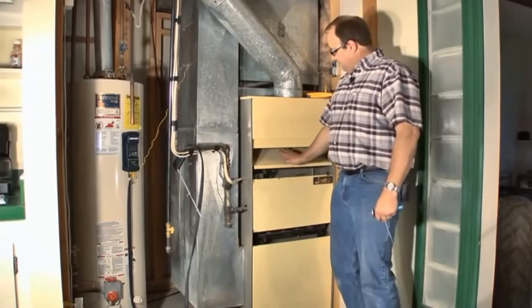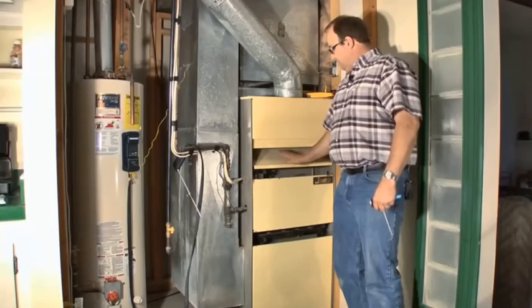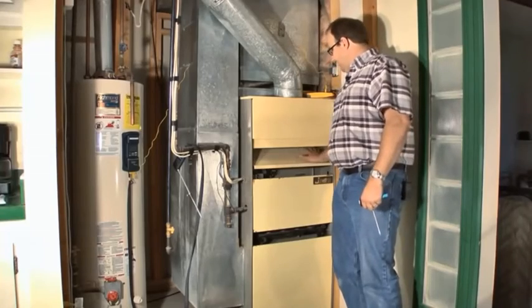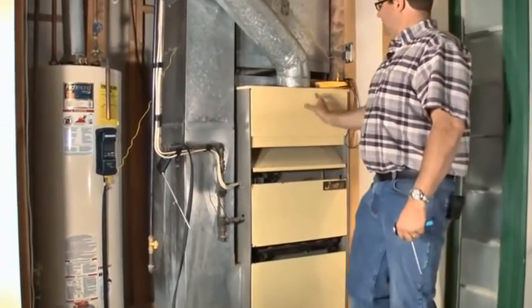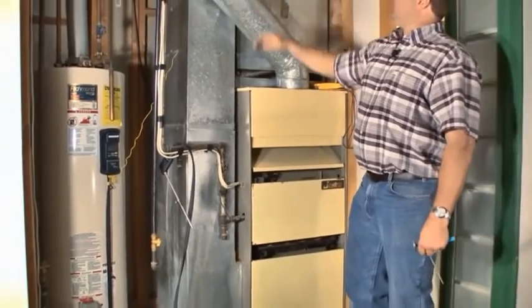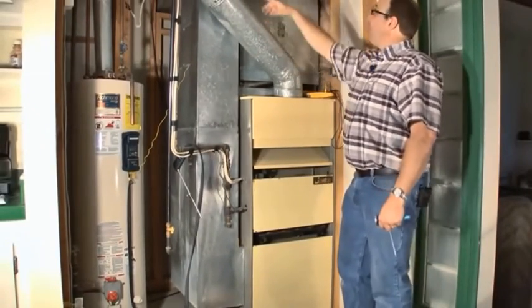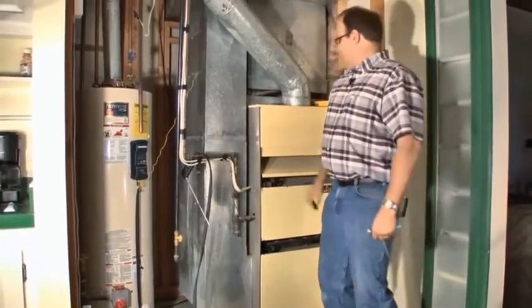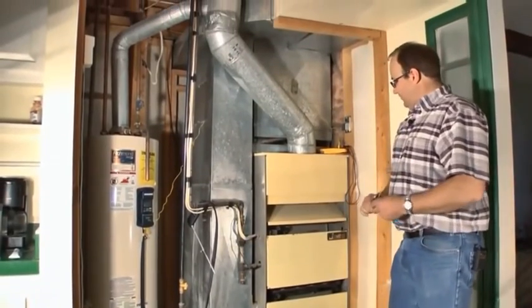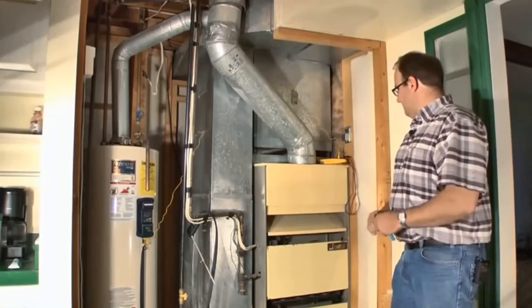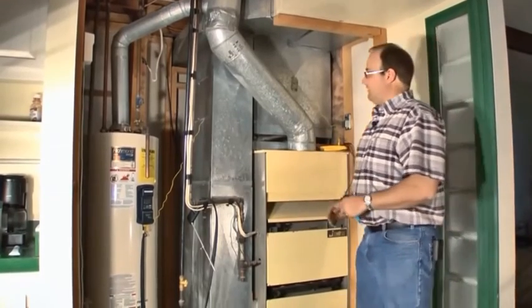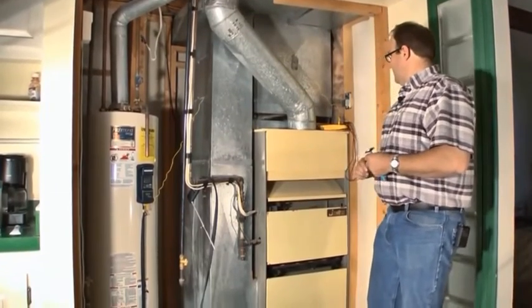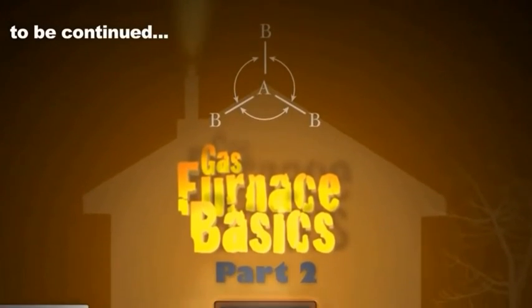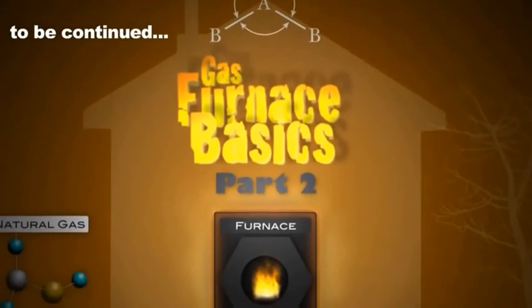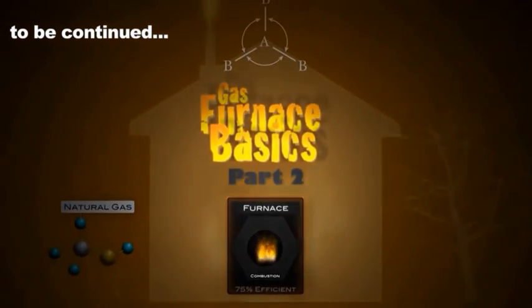This is a natural draft furnace, so the draft hood's right here. It drafts naturally up through the chimney, which is B-vent, and it's probably somewhere between 60 and 70% efficient. We'll get an idea when we take the combustion analysis on it.